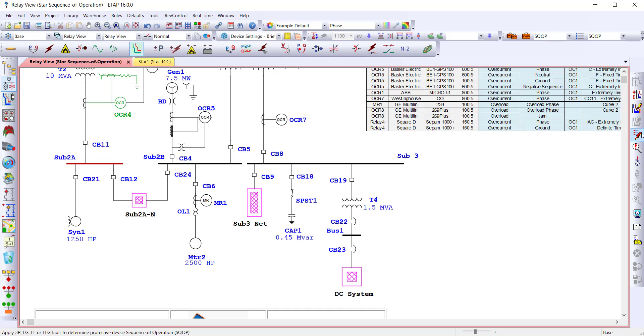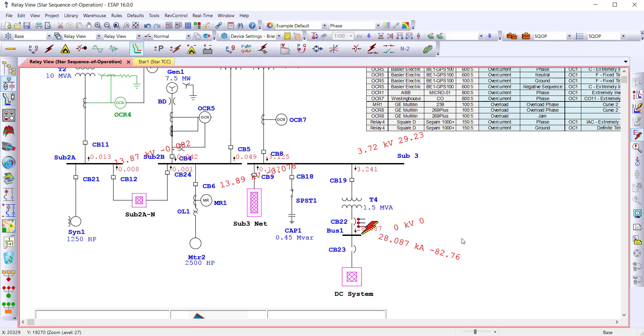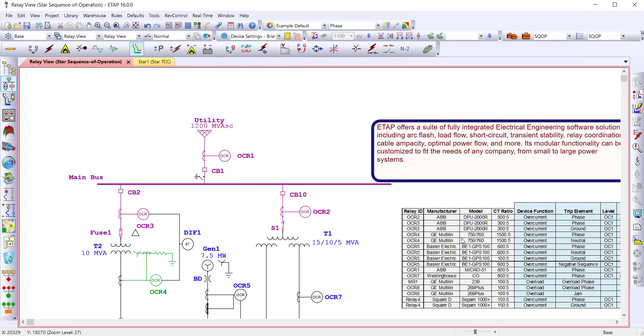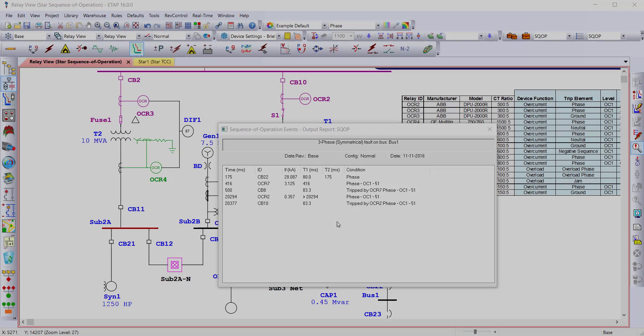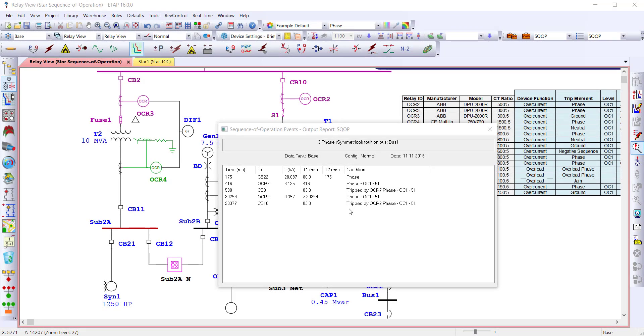Then you use sequence of operation to determine the operating time of the protective devices and graphically animate the sequence in which your devices would trip. The sequence of operation output report displays the through-fault current and the operating time of the protective device.